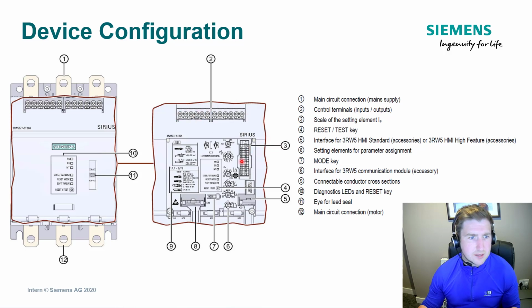Number 3 here is a chart which depicts what you set the operational current to. So they're numbered on here, and those numbers represent different amperages, and this is the table that deciphers that. Number 4 highlighted here is the test and the reset key. Number 5 here is the feed for the standard HMI or the advanced HMI. Number 8 here is the connection for a communication module. That could be for Profinet, Profibus or Modbus.